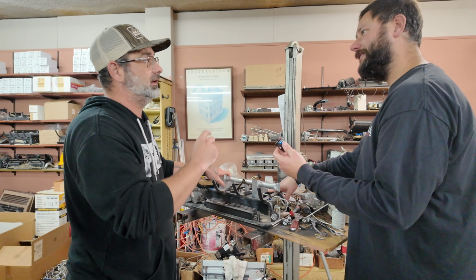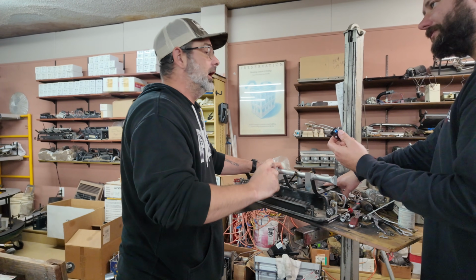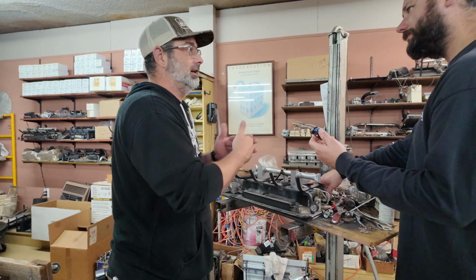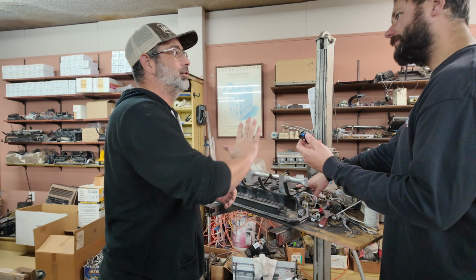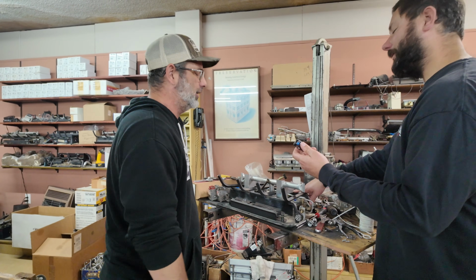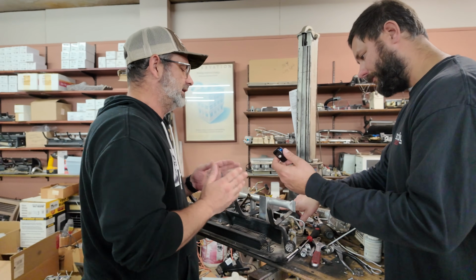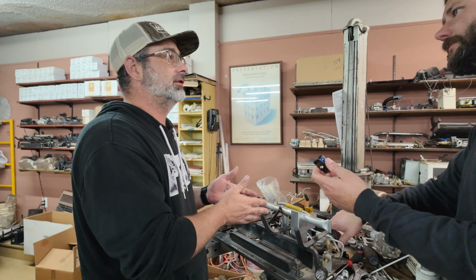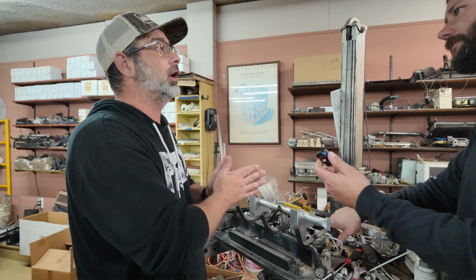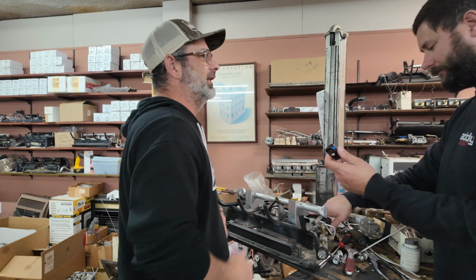It's open and closed. When it senses that heat, it holds it down and it opens that valve up. And then when it cools down, it locks it or unlocks it or closes it, and then you can actually push in to release that gas and everything all over again. And that's one of the biggest issues. Like I said, and of course, they give you that 30-second rule. I've had them actually last almost a whole minute because they were running for so long before it actually cooled down enough to turn off that valve.